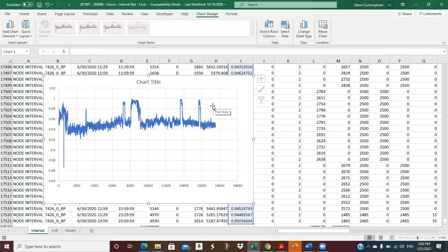When you get billed, is it based on your lowest or your average? The power factor? That's a good question. It's at the time when you set your peak. Well, they actually look at a couple of times, because what usually happens is you'll have your worst lagging power factor, which is caused by inductance, when you have your maximum demand.